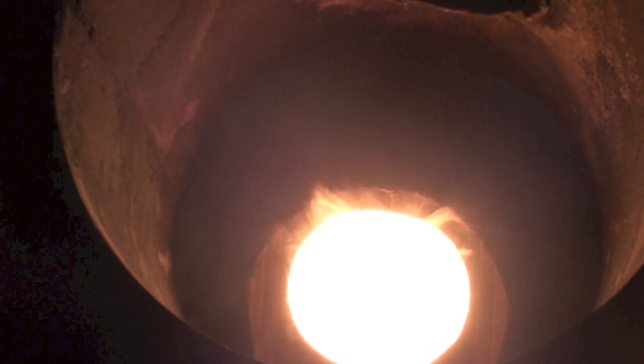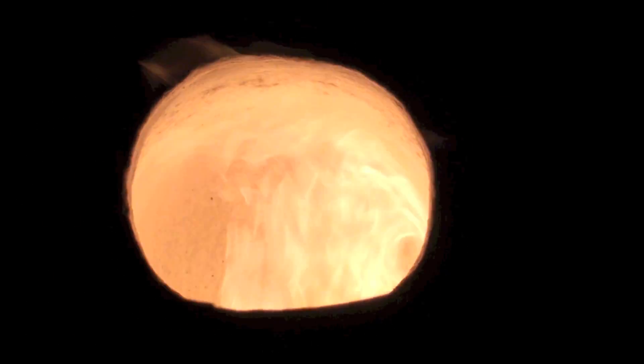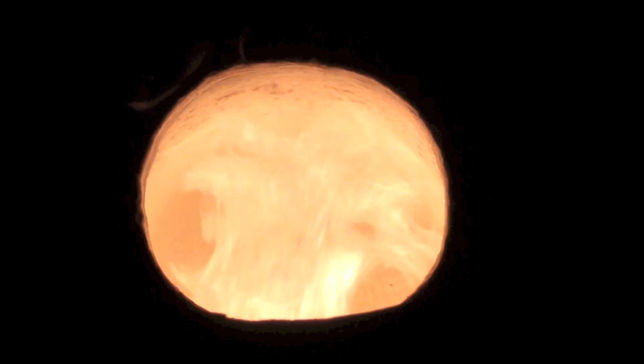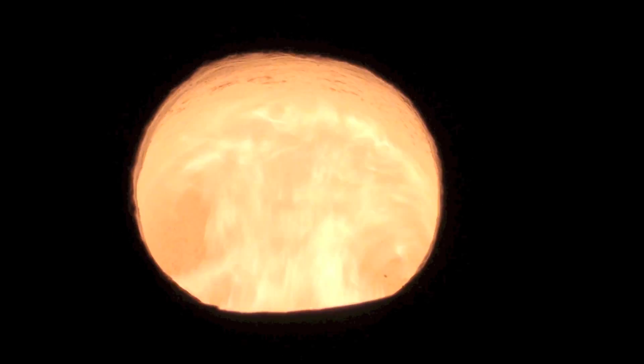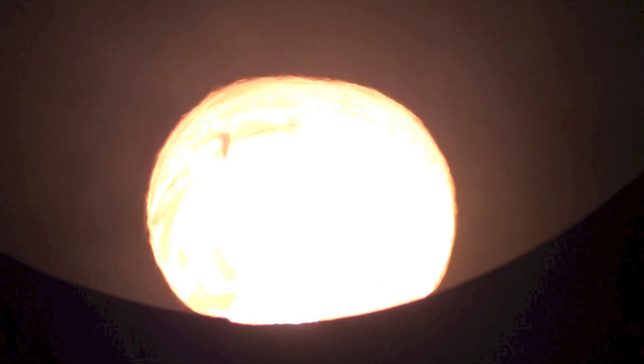This one's on the after fire, or what we commonly call puffing after the burner has shut off. It's usually caused by air in the system or lack of a solenoid on the output of the oil pump to shut off the oil. And if you just watch this thing, you can see what happens when it shuts off.